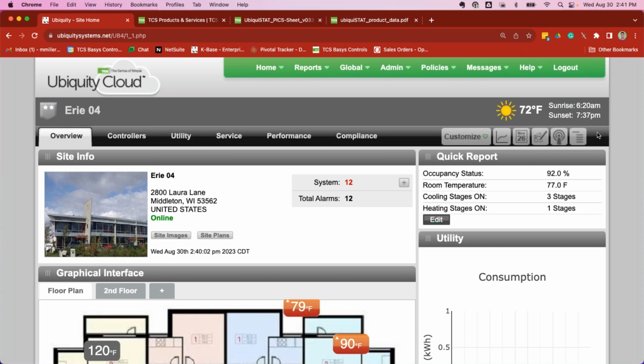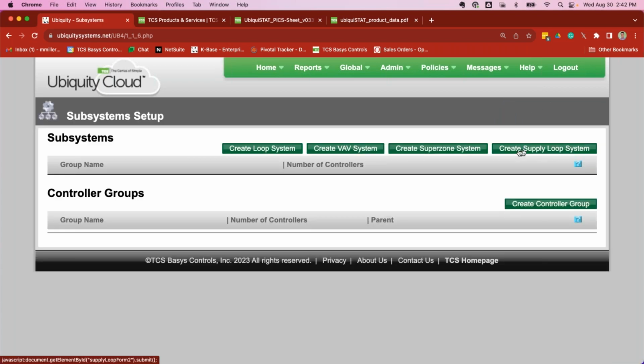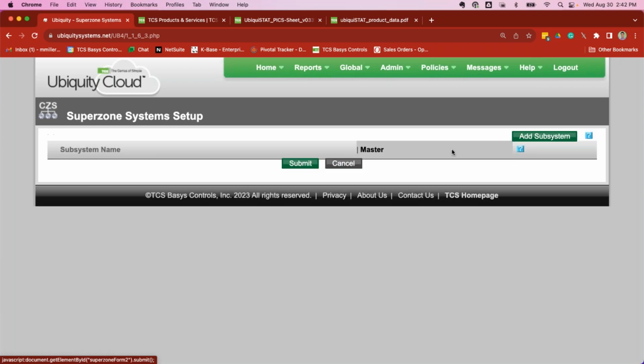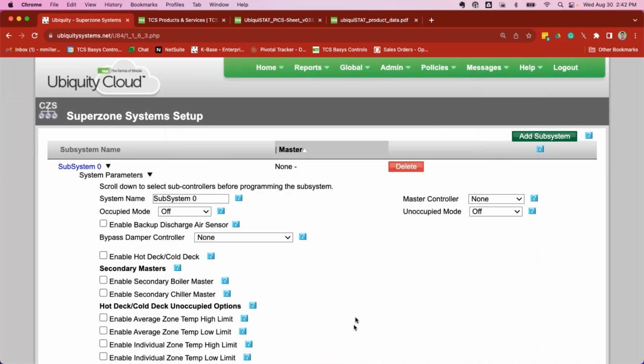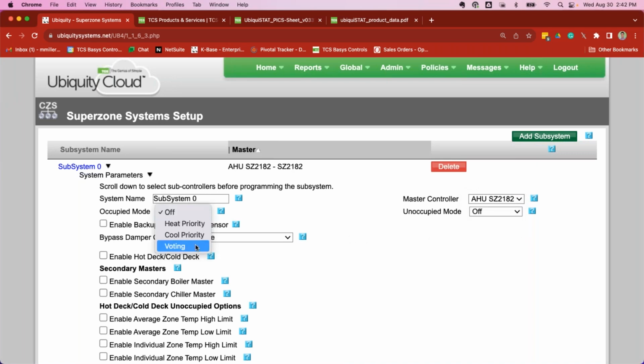Then, when we have more complex systems that go beyond unitary equipment we could just control individually, we have this subsystem page. You can establish loop systems, VAV systems, our superzone system for example, add a subsystem, and choose what you'll use for your master controller, what your zone controllers will be, and whether you're going to set up voting.